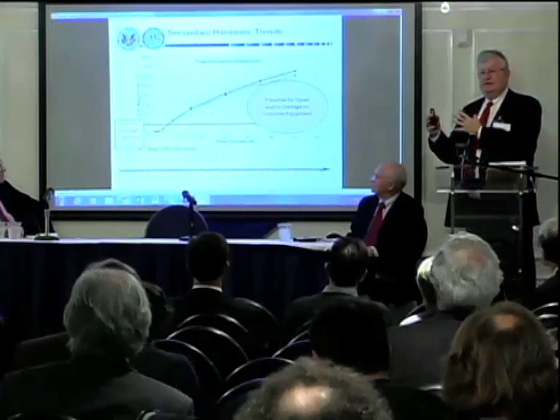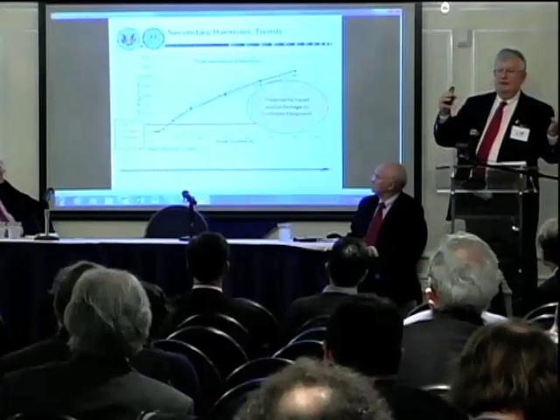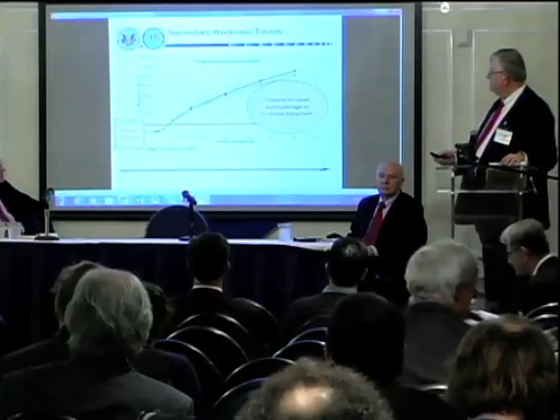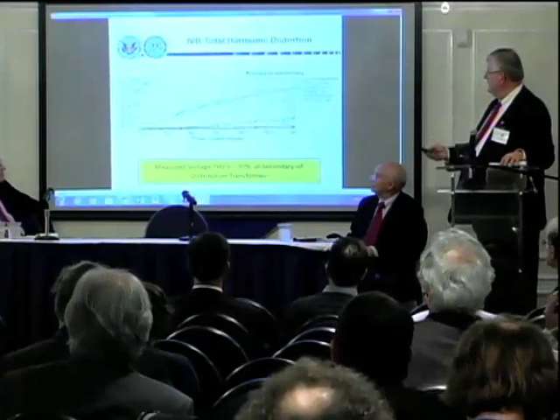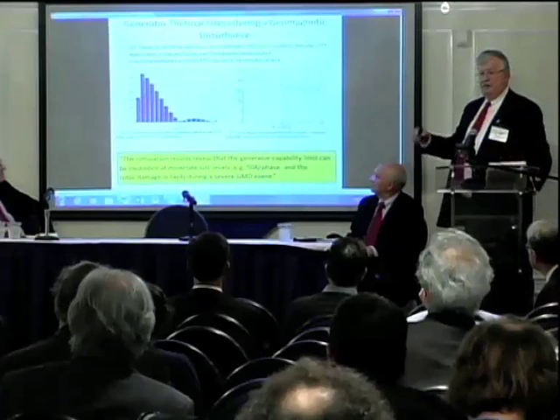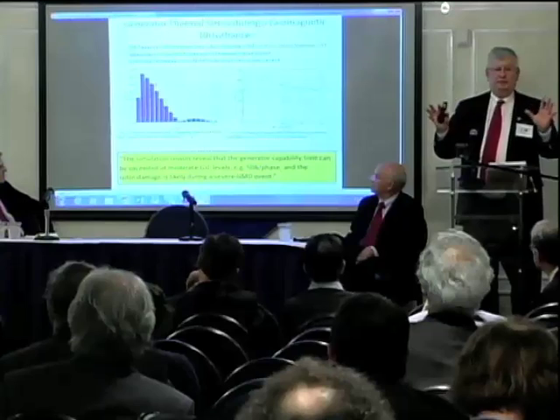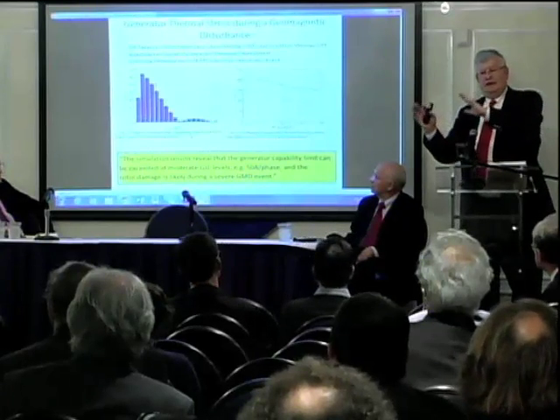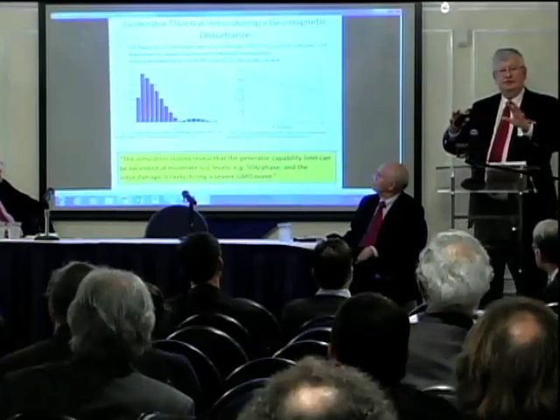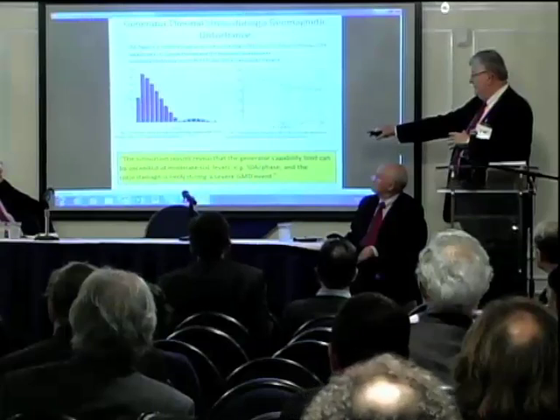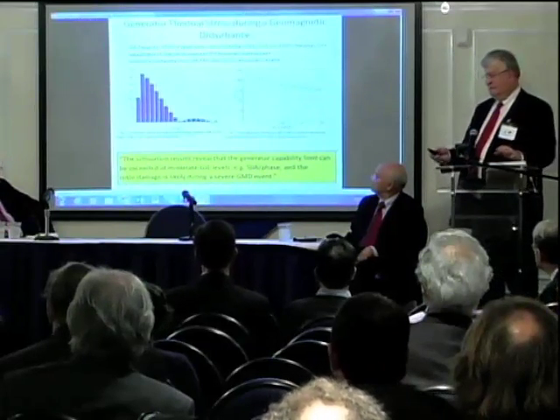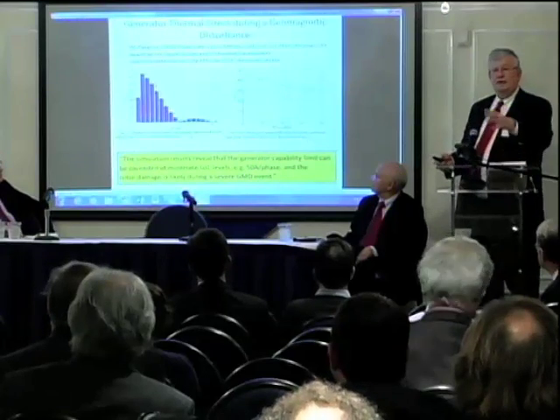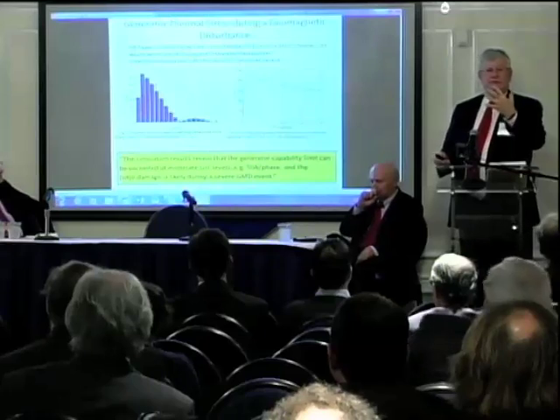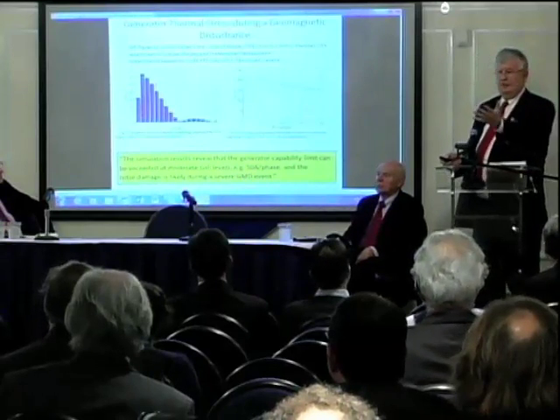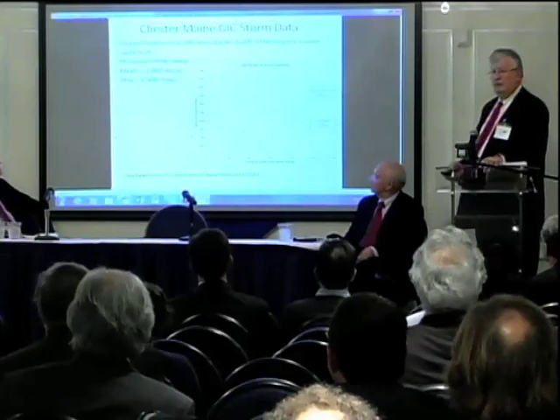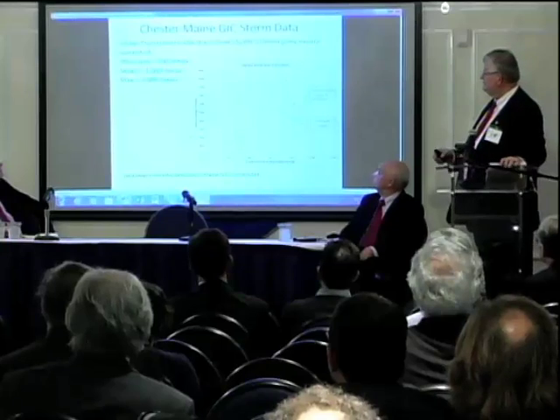That's going to cause damage to equipment, to motors, to rotors, to condensers, et cetera. Louis Marti from Hydro One came out with an IEEE paper that said you're going to have damage to generator rotors if you have more than 50 amps of current per phase. When we are designing equipment, we look at what the maximum credible threat is in order to come up with a design standard.